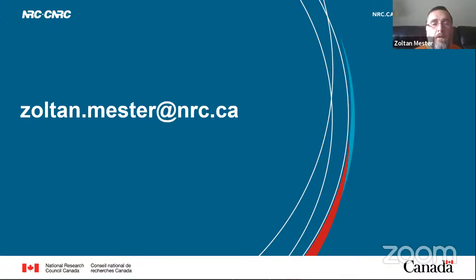So Kelly, any questions from our YouTube channel? There's one question up here on the YouTube live chat relating to the standard dilution analysis. How does any possible time delay or difference between the two traces in the dilution region affect the calibration? Yeah, that is a trouble especially for microwave-induced plasma, which is not simultaneous. You have a little bit of a delay between the traces. One way we deal with that is to take a moving average of the signal. So that helps a little bit with that delay.